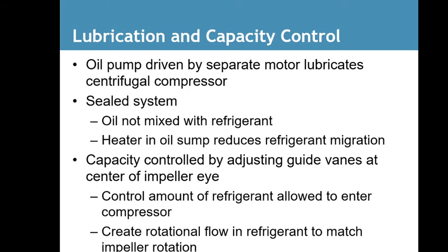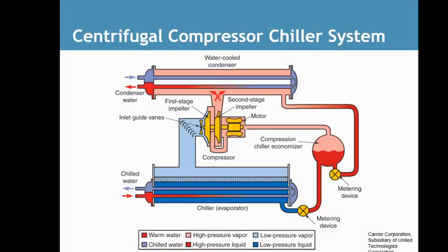Heater in oil sump reduces refrigerant migration. Capacity controls by adjusting guide vanes in the center of the impeller eye. Control the amount of refrigerant allowed to enter the compressor. Creates rotational flow in the refrigerant to match impeller rotation. Here's a diagram of a centrifugal compressor chiller system.